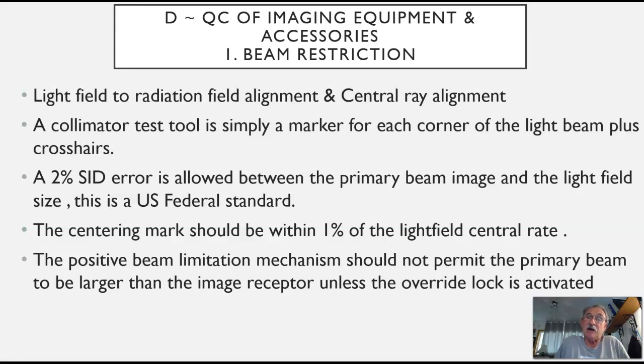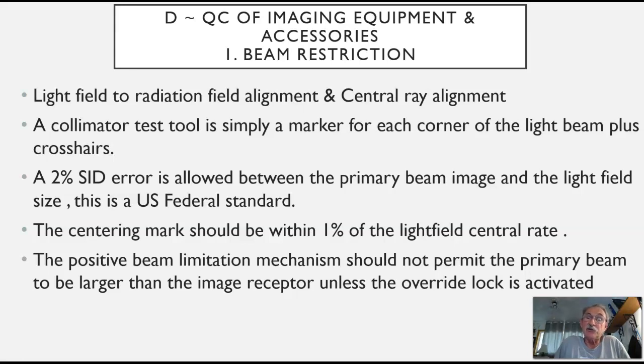Another one of these tests is the positive beam limitation mechanism. Positive beam limitation is that mechanism where you put an image receptor into the Bucky — it recognizes the size and orientation of that image receptor, and it opens the collimator exactly to that size automatically. The intent is that the primary beam is no larger than the image receptor, unless we activate the override lock, which is the exception and not the rule.